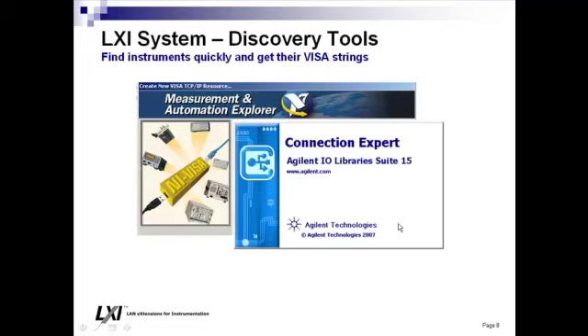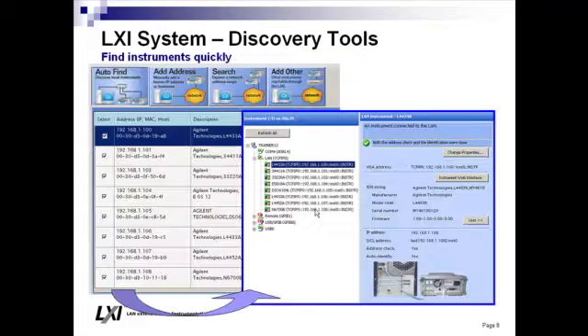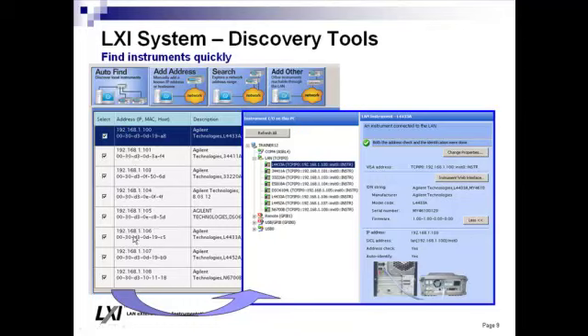How would you know what those descriptors are? The Connection Expert in Agilent's I/O library, or NI's Measurement and Automation Explorer (MAX), can help. Agilent's Connection Expert allows you to find instruments quickly — the AutoFind capability discovers all LAN-based instruments that adhere to the LXI standard protocol. Once discovered, you can populate your LAN tree and find the VISA address for each instrument to use in your program instead of the GPIB designation.